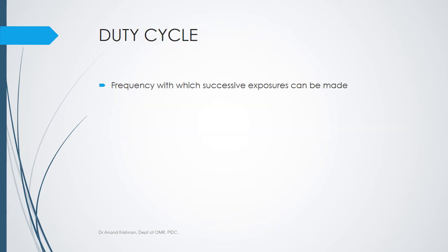I mentioned to you before regarding the duty cycle, where I talked about alternating current, where we use only one half of the alternating current to produce the necessary electrons and the intensity of electrons that we need. The other half is actually not required. So this puts a restriction on our ability to produce constant bursts of X-rays.